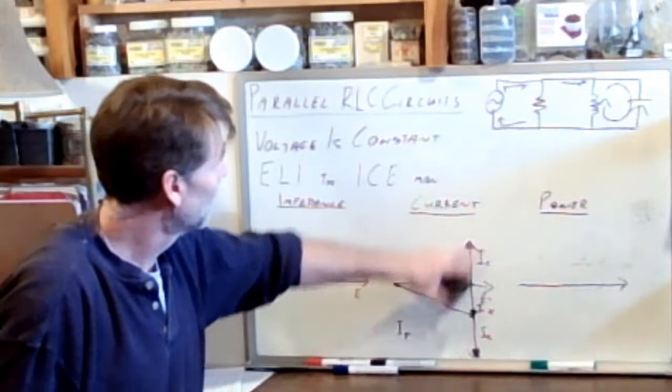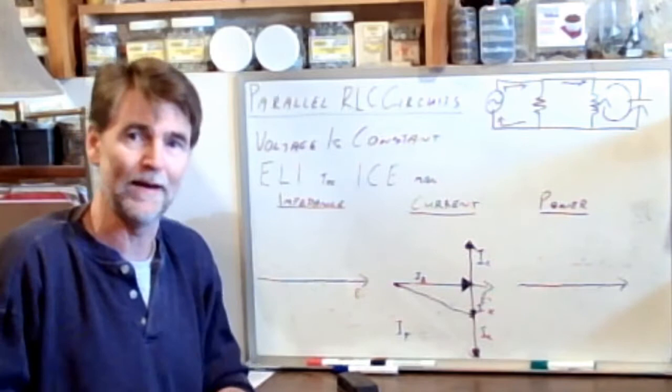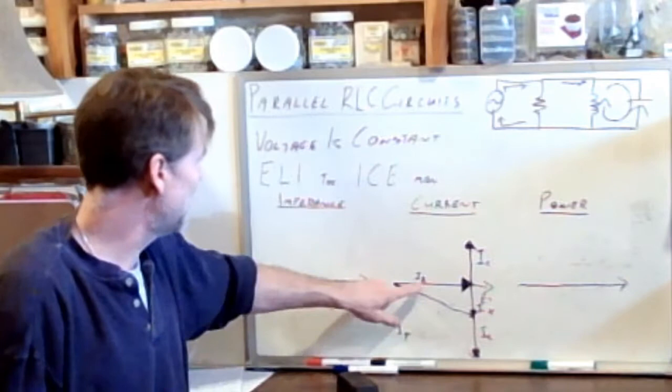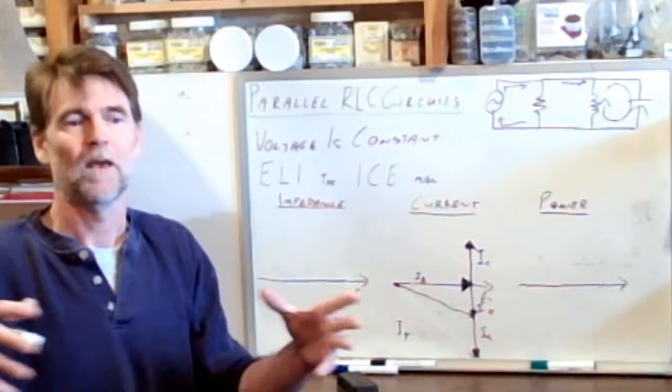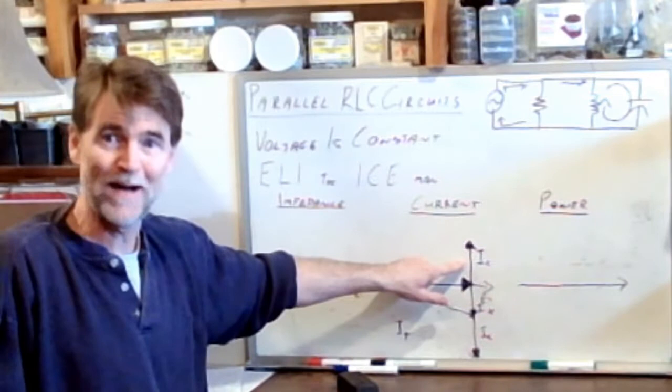So quite I mean now it's all automated. It used to be that it was all done manually that the electrician, the maintenance guy, he'd come to work in the morning and the first thing he'd do is he would take a look at the power factor meter. So there's actually a meter as part of the electrical equipment measuring this angle and reporting the power factor. And as parts of the plant come online or go offline and we add or remove inductive loads, we will need to add or remove capacitive loads as well to match.